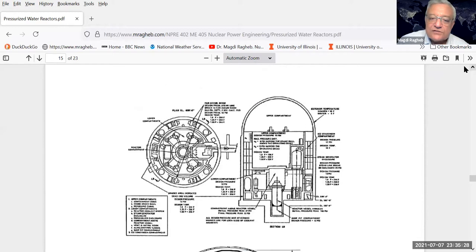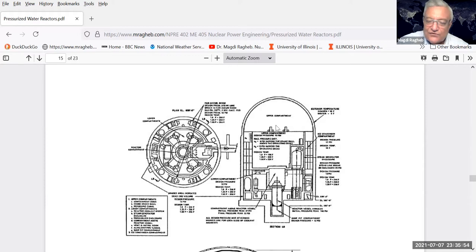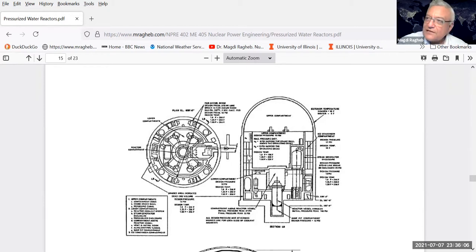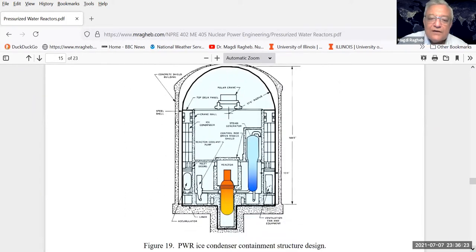There is another type of containment structure called the ice condenser containment. In that case, you build a refrigerator inside the containment and produce literally ice. The ice, instead of having a containment spray, would condense any steam in the case of an accident. It is costly to keep the ice in ice mode without melting. The real containment is the steel shell, and what it contains is where steam is contained in the case of an accident. The outside is a biological shield - a concrete shield building meant to protect the reactor internals.